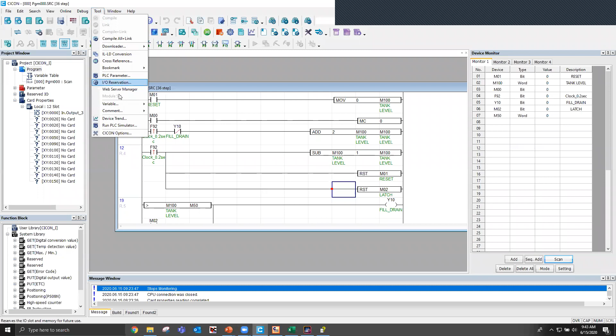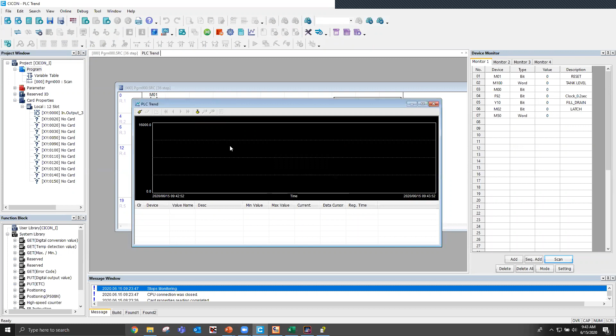To get here, go to Tool, Device Trend, then right-click, Insert, and that's where you insert the device you want to monitor over a given time. Make sure you change your max value accordingly, and once done, it will start recording the data. Once you disconnect from the PLC, it will no longer show those values—you'll lose the whole trend graph.